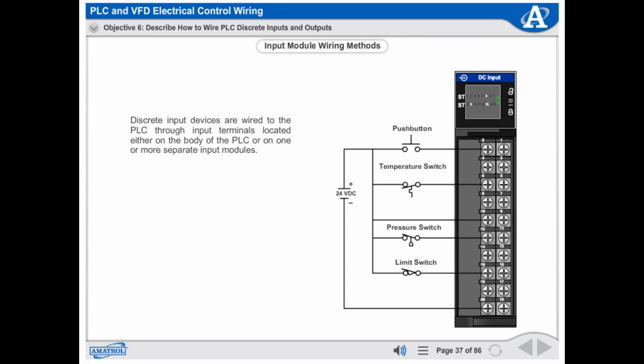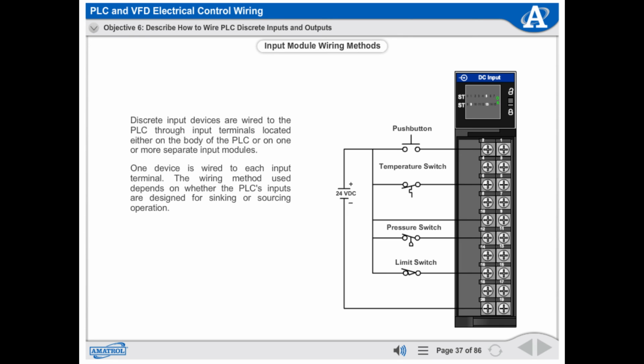Discrete input devices are wired to the PLC through input terminals located either on the body of the PLC or on one or more separate input modules. One device is wired to each input terminal. The wiring method used depends on whether the PLC's inputs are designed for sinking or sourcing operation.